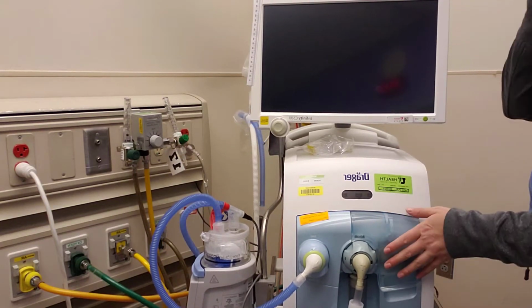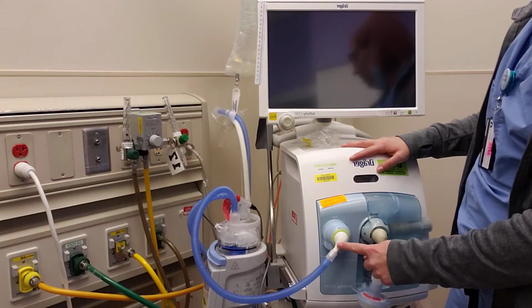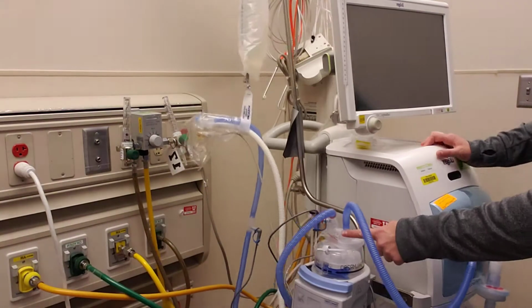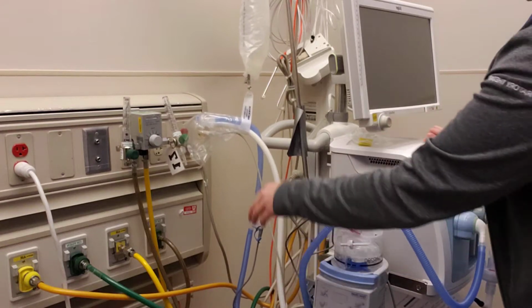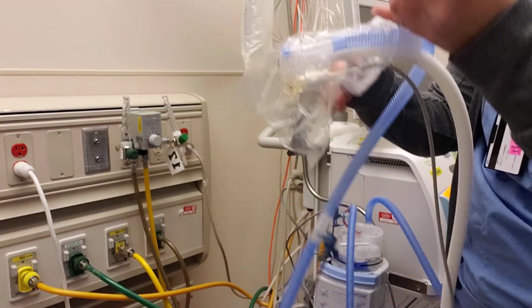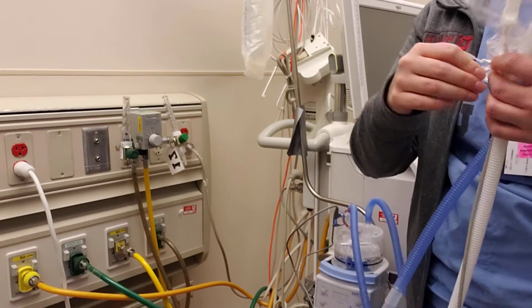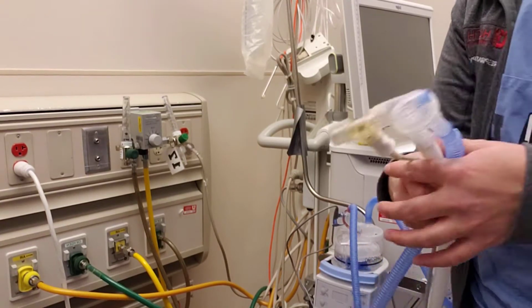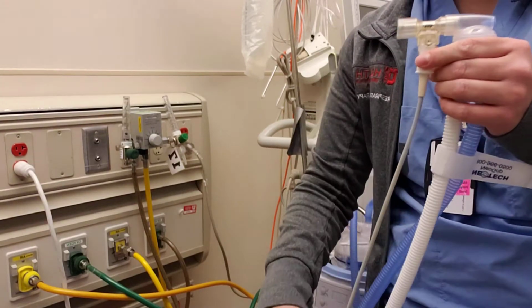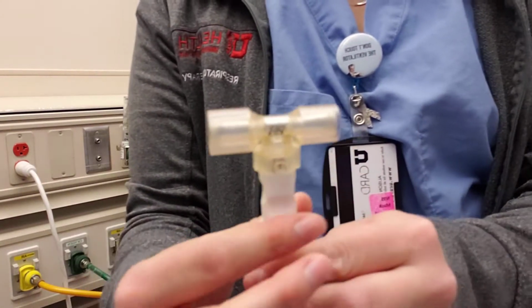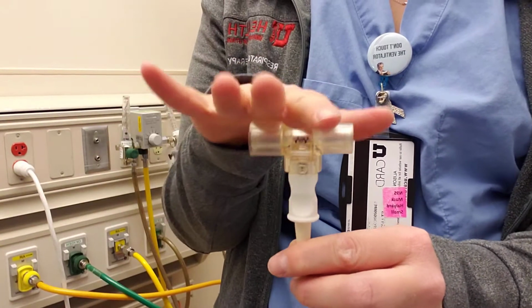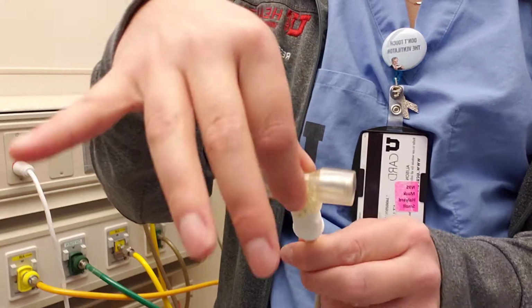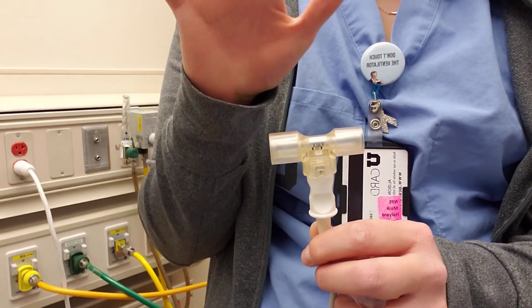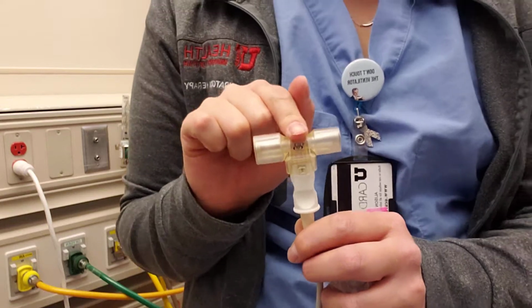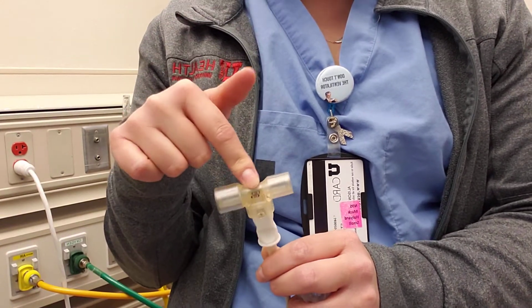And then up in the front, we have our air outlet to a heater, which then comes, let me take this baggie off, to our Y. And notice this cable and this adapter. This is your proximal flow sensor. This lets you know what your return volumes are, and basically what your baby's doing. The proximal flow sensor can be a little bit touchy, so don't feel afraid to replace it or calibrate it, or sometimes if you just tap it, it'll get some condensation out.